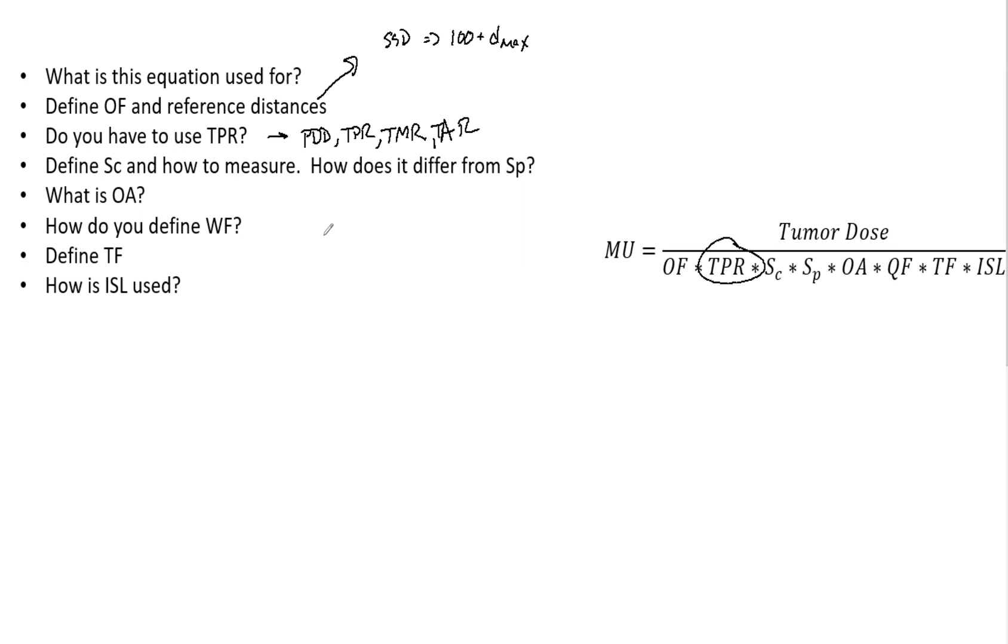SC and SP. SC here is the collimator scatter factor, which depends on the field size defined by the collimators. This must be measured in air with a buildup cap at a reference distance, which typically is 100 cm.